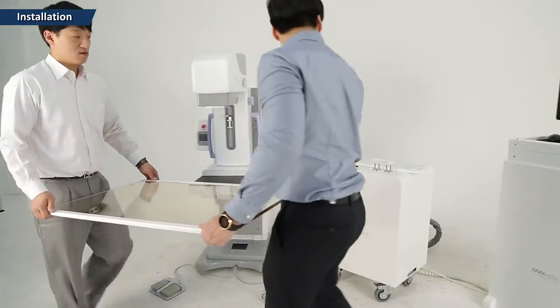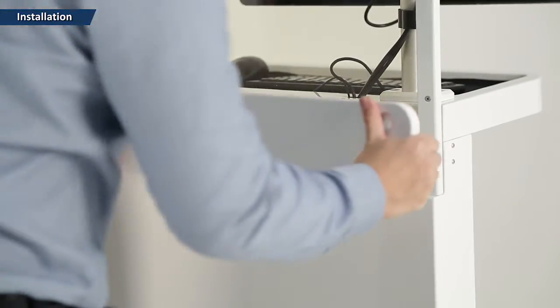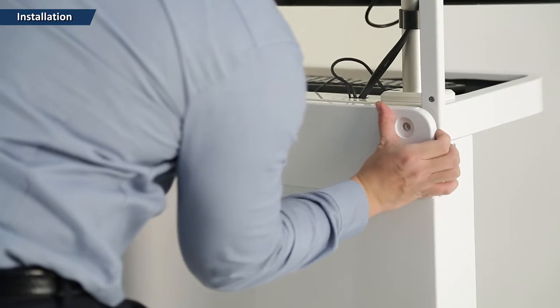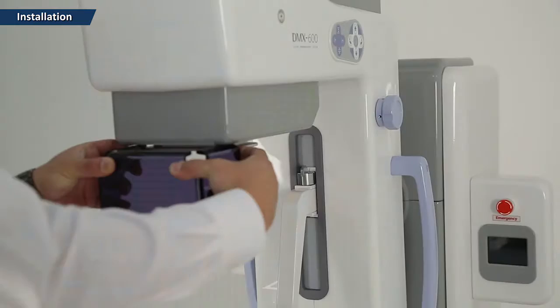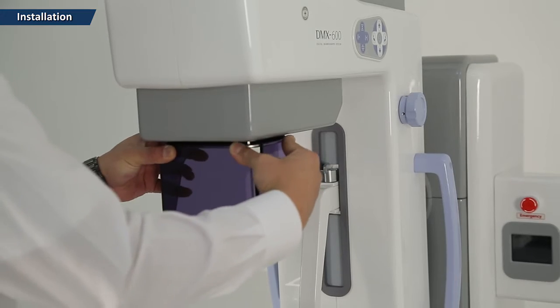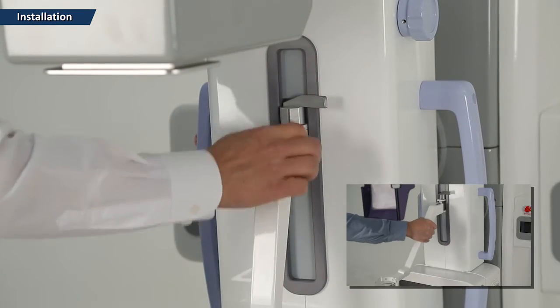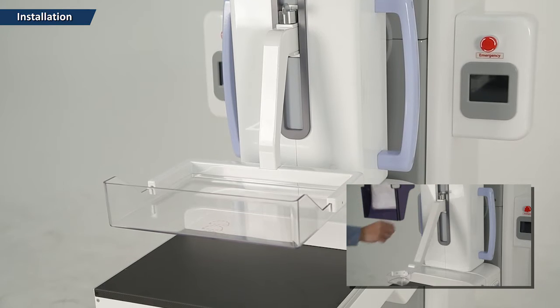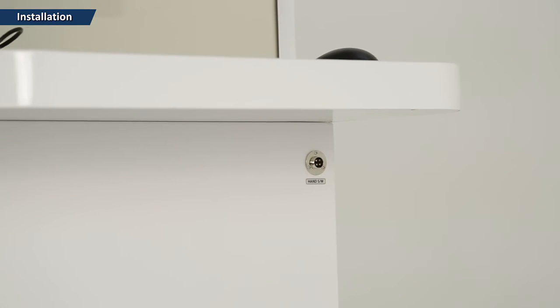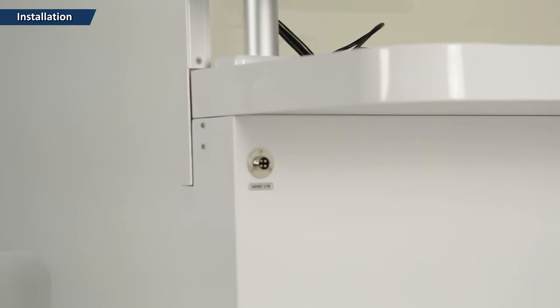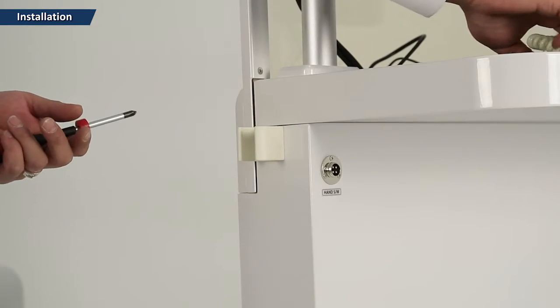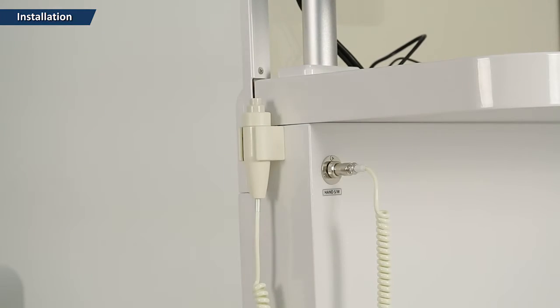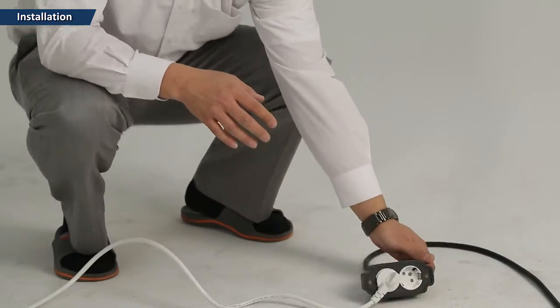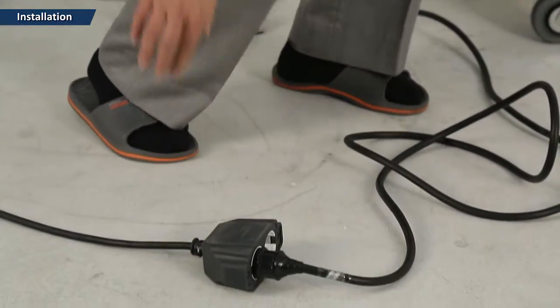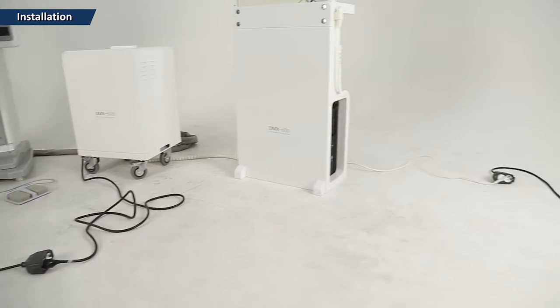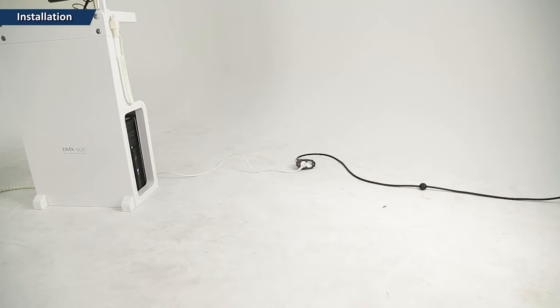Install the lead glass. Because of the risk of damage, it is advisable for at least two or more people to collaborate. Attach the accessories, face guide, pressure plate. In case of the hand switch, install it according to the user's convenience. Lastly, connect the power supply. The main power supply and the PC power supply should be connected to separate power sockets.